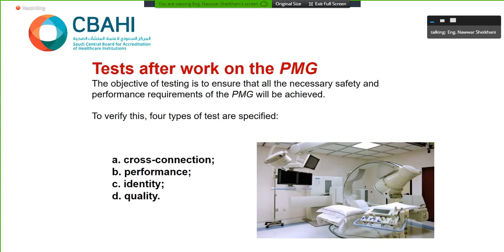While talking about cross connection, if you have, for instance, 4 lines of medical gas, and you are doing some repair or welding or a new line, you have to shut off three gases or 3 pipes to test the 4th one. You cannot make the 4 open, close the 3 and test the 4. Then close number 4 and number 3, 2, and test number 1, and so forth. So close the 3 and test the 4th one. So that's why we have to organize ourselves.